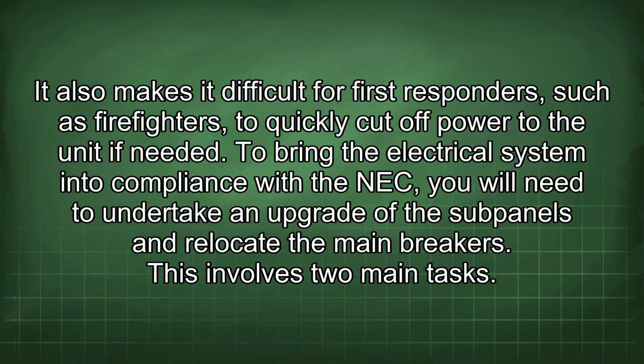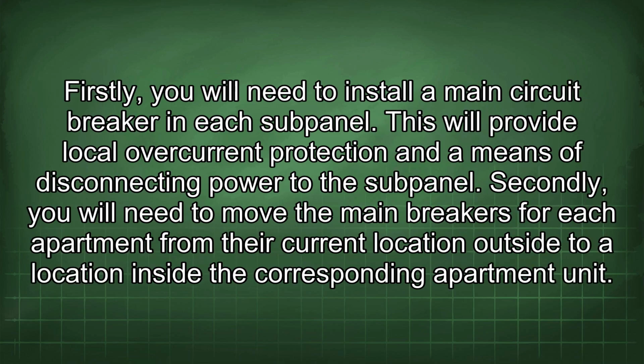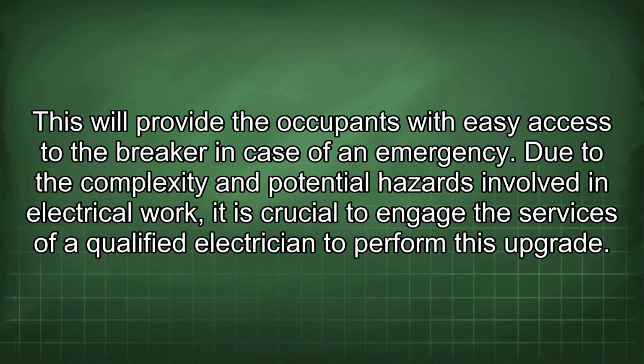To bring the electrical system into compliance with the NEC, you will need to undertake an upgrade of the subpanels and relocate the main breakers. This involves two main tasks. Firstly, you will need to install a main circuit breaker in each subpanel. This will provide local overcurrent protection and a means of disconnecting power to the subpanel. Secondly, you will need to move the main breakers for each apartment from their current location outside to a location inside the corresponding apartment unit. This will provide the occupants with easy access to the breaker in case of an emergency.